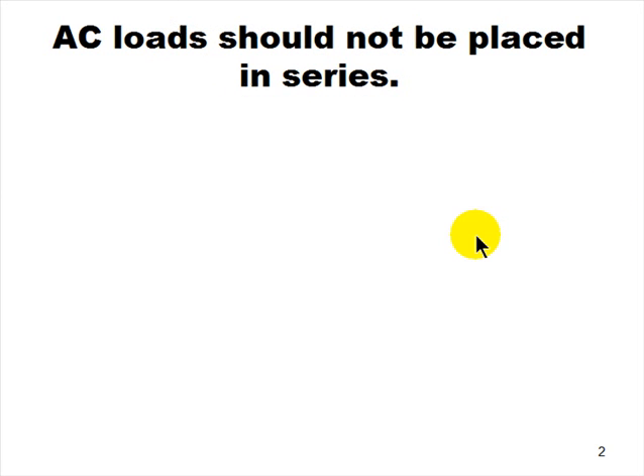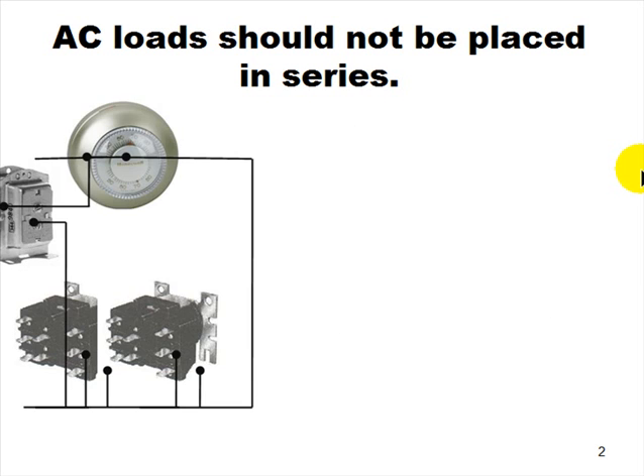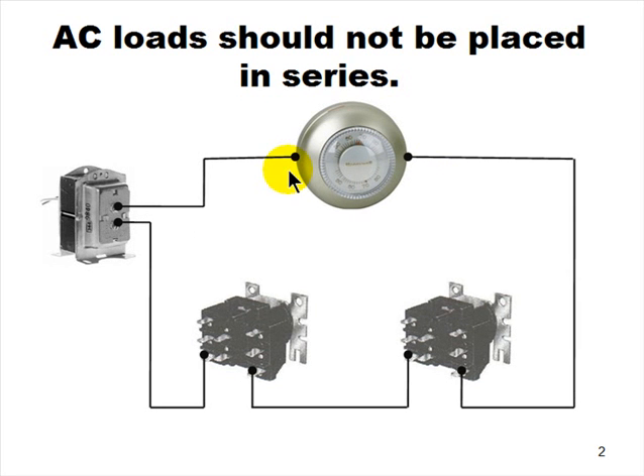Why is this important? Well, let's give you some relevance here. AC loads, alternating current loads, should not be placed in series, at least the AC loads we deal with. Here's what happens. T87F thermostat, AT72D transformer, 24 volts output. Hook it up, let the thermostat call, and you're going to get that. Because this is 24 volts, and if these 2 coils, solenoids, on these relays are exactly the same, you'll have a 12-volt drop across each of them.